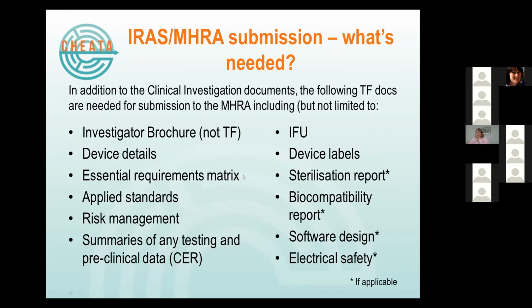There's quite a lot to send to the MHRA in line with this submission. These are some of the key documents: an investigator's brochure, which is not part of your technical file, but all these other documents, device details, your essential requirements matrix, standards, the risk management, the summaries, are all parts of your technical file. So if you've been doing your job right from the get-go and compiling all of these documents, by the time you come to do the clinical work, you should be in a reasonably good place. And you can say I've included the sterilisation report, the biocompatibility report, anything on software design and electrical safety, which you will need to submit to the MHRA.